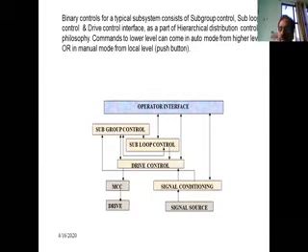It may be single phase or three phase. This MCC will take care of the electrical signals: under voltage, over current, phase failure. If it is three phase, feedback will be taken in the MCC room.